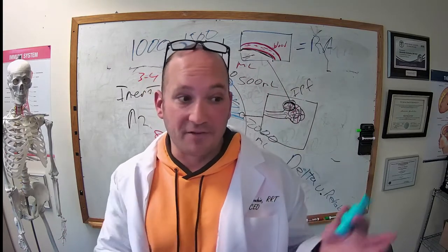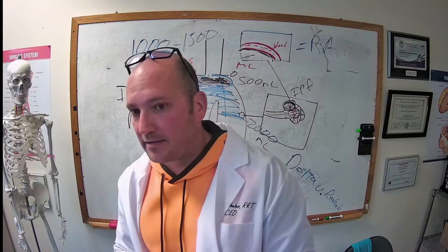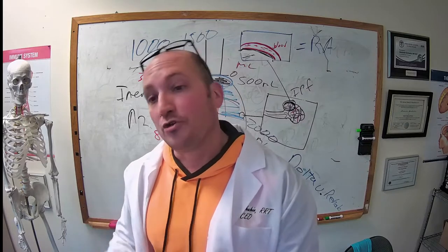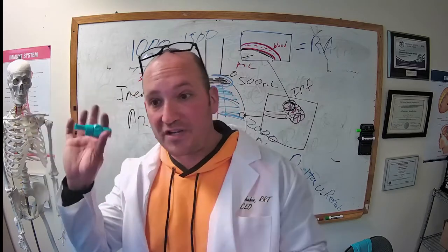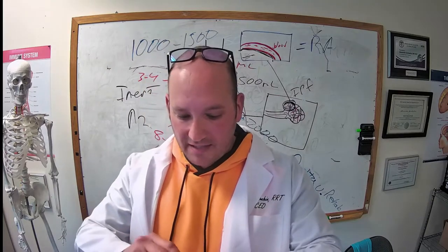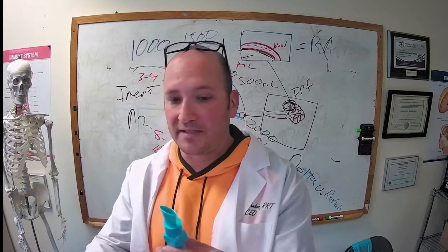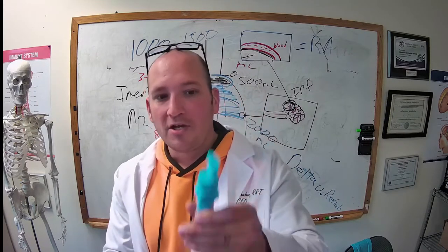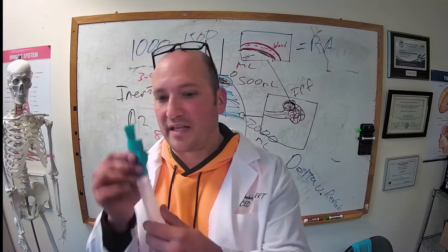Now, a setting of 5 for some people might be tough, right? So you use the incentive spirometer to see what setting you should be at, and then at that point you can do a freestyle. That's the reason for attaching to an incentive spirometer. The other reason is you don't have to replace the mouthpiece. Meaning you have that other mouthpiece that came with the incentive spirometer, you replace it with a Delta V. All you have to do is set the Delta V to a 0.